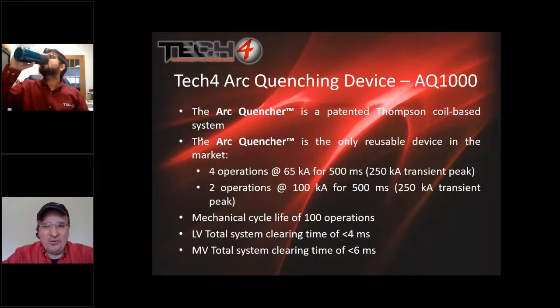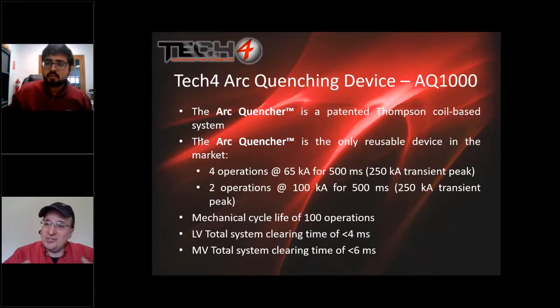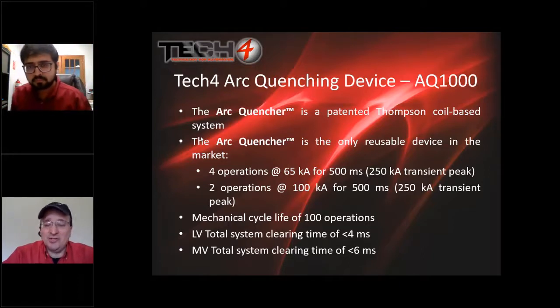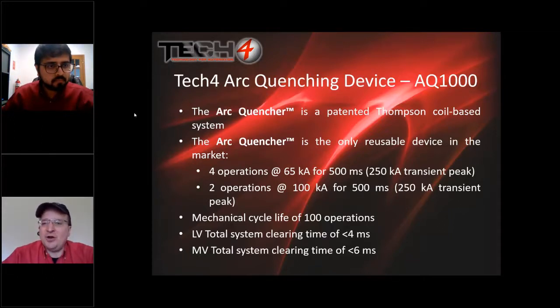So the point I want to make is, in addition to the resettability specifications you see on the slide, if in your facility you have more than 1 arc flash event on the same circuit, you probably won't have to worry about resetting the arc flash quencher even a second time. You're going to have to worry about getting your resume ready, because someone who owns that facility or is responsible for risk management and liability issues will be asking why repeated persistent arc flash events are taking place.